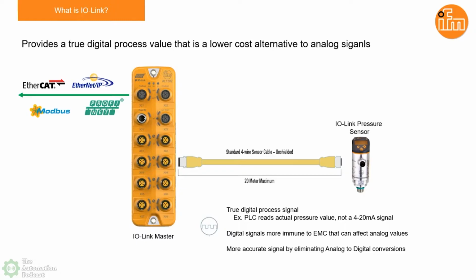With an IOLink sensor, we are sending a digital value back to the PLC via the IOLink master. This true digital process value is a really interesting and lower cost alternative to an analog signal. What I mean is, from the PLC's point of view, you're no longer receiving a 4 to 20 milliamp signal or an on-off signal. What you actually get is the true scaled value of the sensor itself. I'll show you in the next PowerPoint what that truly means.